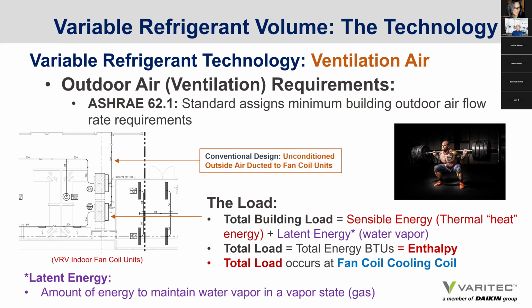But that begs the question, certainly in Phoenix, Arizona, what about the outside air? We have to bring a minimum of outside air to a building to conform with ASHRAE Standard 62.1, which defines the minimum ventilation rates required at each zone depending on that zone's usage and building application. Well, a conventional approach to outside air is to run an outside air duct to a louver on a wall or to an intake hood on the roof, and just draw the outside air through the negative pressure generated by a return duct to the fan coil units, and hope you get the right outside air to each fan coil as necessary.